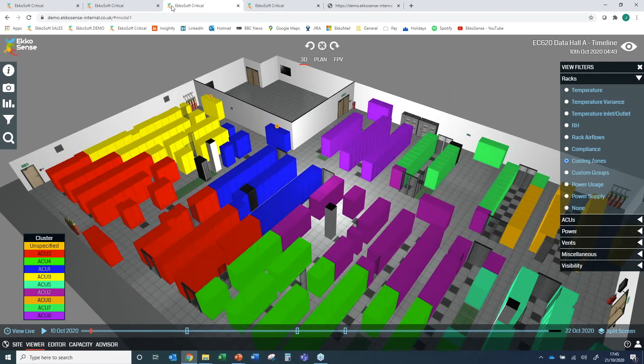It's linking the rack data and the cooling data, learning for each rack which cooling units cool it and to what level. So it constantly learns the capacity within the rooms, not just as a total room, but within areas and pockets of the room, where my actual capacity and availability are.